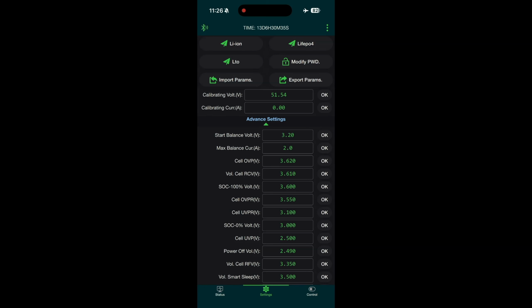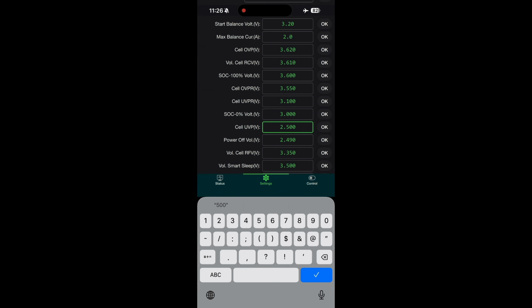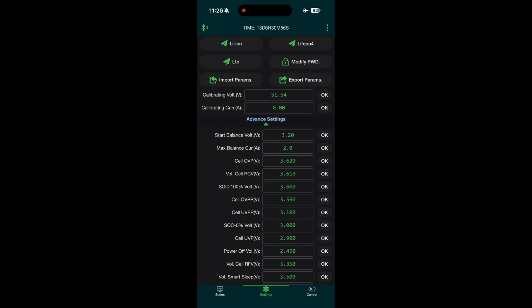What is the absolute bottom end of charge that you want? 2.5 is typically the lowest voltage listed on most spec sheets for your cell, but I set this to 2.9, again to try to maintain around that 80% depth of discharge.